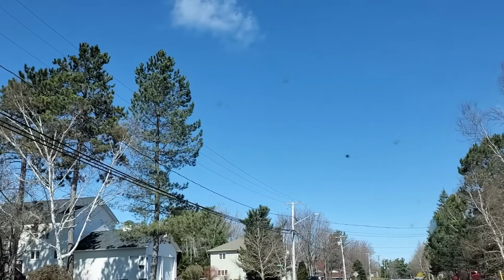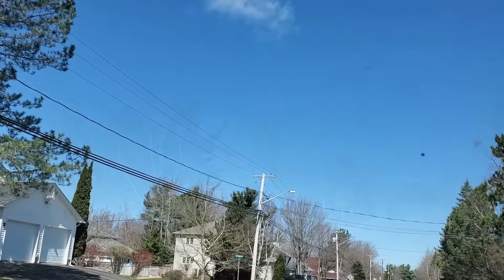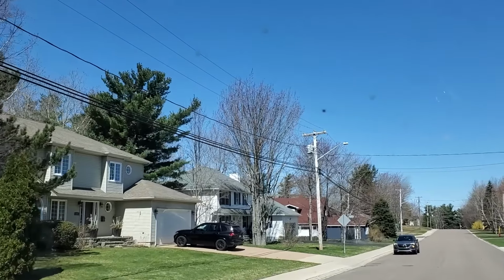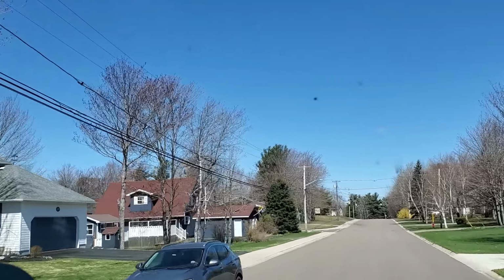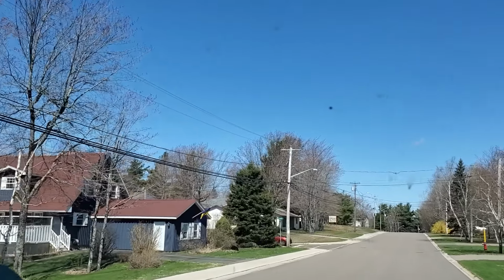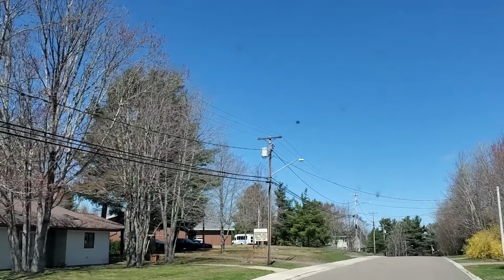If there is phases slapping, we're looking for some slack spans. We're also looking for trees, of course, animals. Maybe a phase came untied from a pole. Quite a few slack spans in this area.